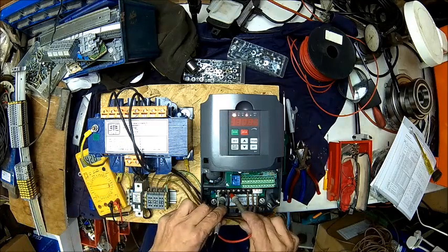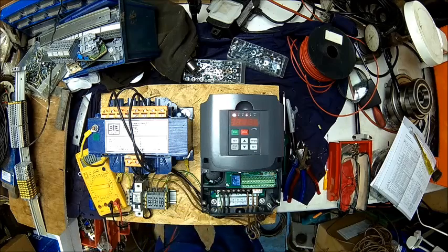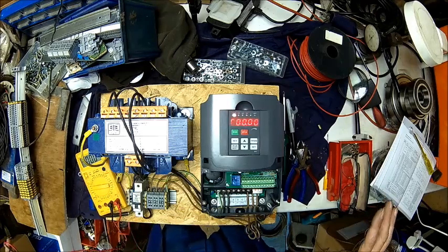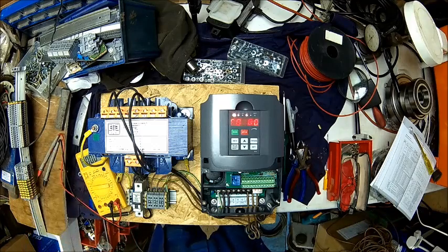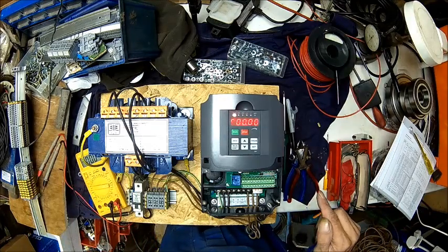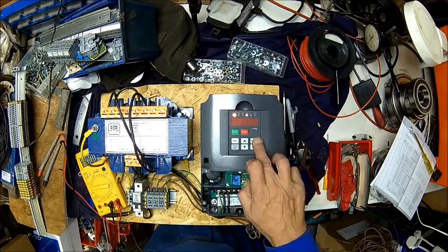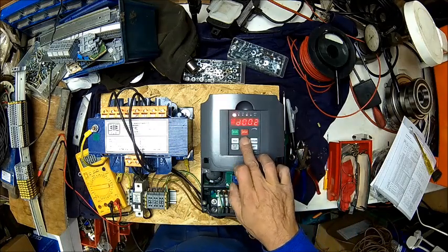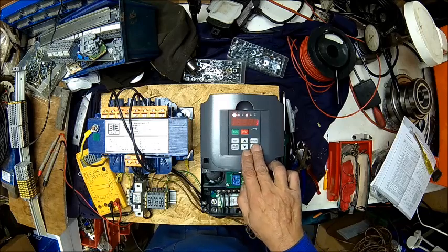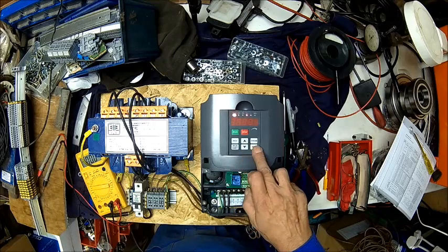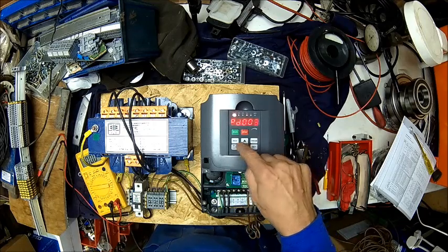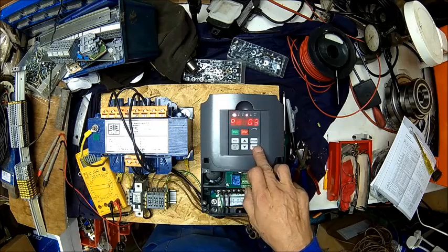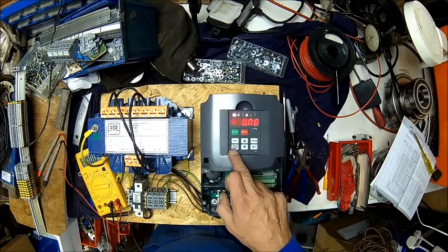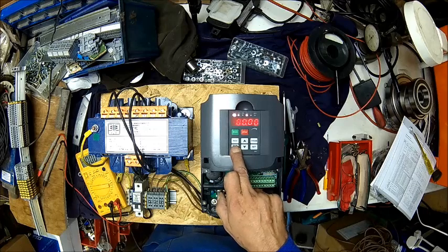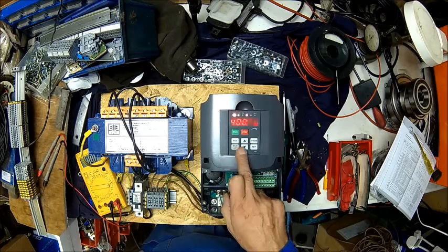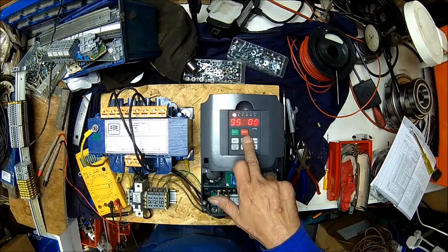is about 440 something. Okay, so first of all, this is a brand new inverter. We need to set some parameters, because when they come, they usually set to some weird frequencies. Just need parameter 2, I think. So that's we want the panel. So that's frequency on the panel. Parameter 3 is maximum operating frequency. That's set to 400 Hertz. That's no good. We want 50 Hertz. Or make that 55 or so. I'll make it 55. That's fine.